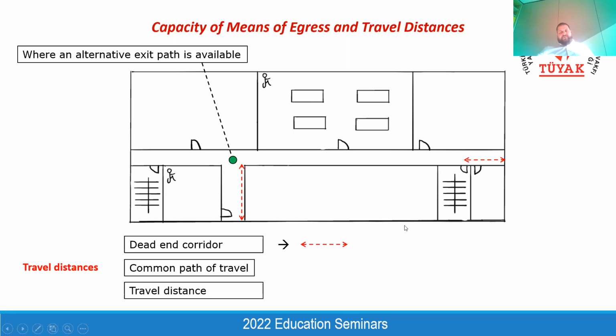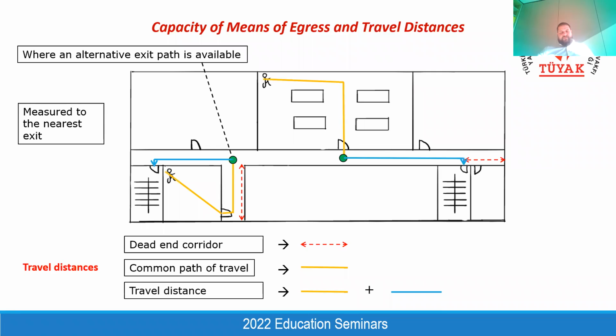It is also a reminder for the travel distances and the measurement of the travel distances. It is very stringent, as per Turkish fire code and also as per international standard. Especially the dead-end corridor and the common path of travel become very stringent if you don't have a sprinkler system. As I said from the beginning of the presentation, even if the building is not high-rise, even if the building is not required to be sprinkler protected due to the construction height or building height, you may require a sprinkler system to make this design more efficient.